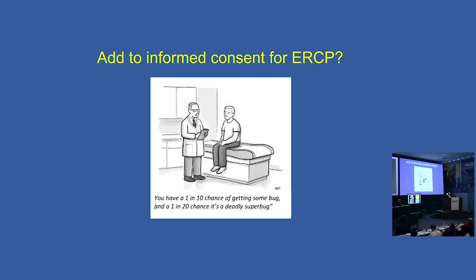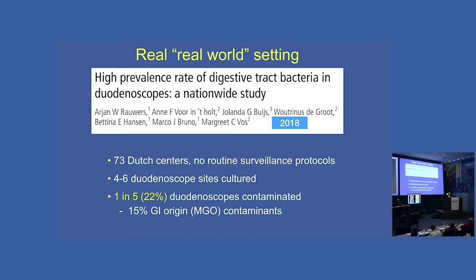But that's not even the real world setting. This is the real world setting. And this is a study from Holland. And in this study, 73 Dutch centers, there was no routine surveillance protocols being performed. In other words, no one was being observed. There was no Hawthorne effect. There were 4 to 6 duodenoscope sites cultured, and it showed that 1 out of 5, actually more, 22% of the duodenoscopes were contaminated. And of those contaminations, they identified that 15% had a GI origin. So those are potentially those superbugs that we're talking about. So now we're talking about a 1 in 5 risk of getting an infection.